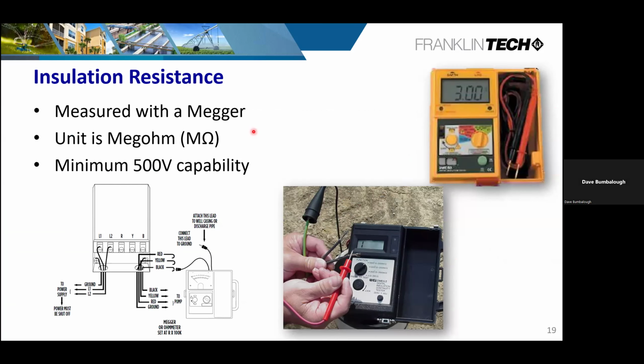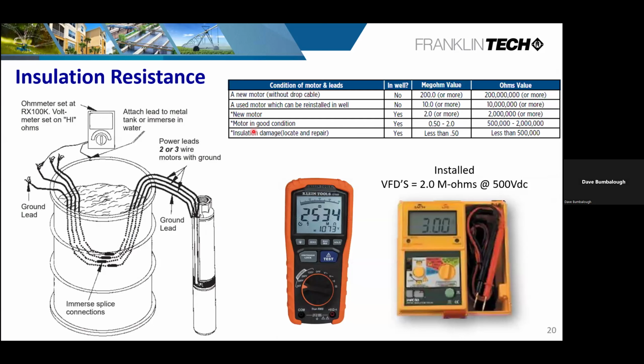An insulation test, I've got to say, is the best way of determining any kind of breakdown in the wire. When you're doing a splice kit, honestly, I would probably have taken that motor and pump and put it in that barrel of water too and tested it all as one unit. But you can check when you do your splices. Sometimes we will do those in-house before we take it to the job site. One of the things I always suggest, before you splice or tape that splice up or shrink tube it, is to clean it. Oftentimes we overlook the simplest things, and if we clean that lead, that assures the adhesive is going to stick a lot better to that material and is less likely to have any issues.